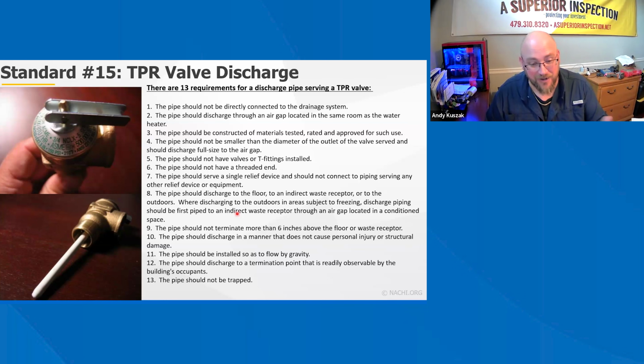The discharge pipe that I'm talking about looks exactly like PVC, but on it, it says specifically, rated for temperature pressure relief valve at this temperature, at this pressure, and so on and so forth. Where you used to be able to tell, just like with screws and nails, oh yeah, that is definitely not galvanized, or that's definitely not rated for treated wood, you may or may not be able to tell the difference on discharge pipes. If it's plastic or PEX or PVC, if you really want to dive in deep, you really need to pull up the manufacturer and see what it's rated for.